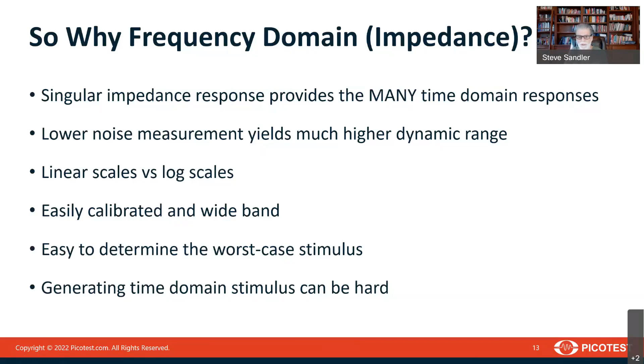So in a vector network analyzer, we don't actually have to worry about generating that stimulus, and in time domain we do. And most of the time we're measuring low impedance. That's not always true, but most of the time, at least in power, we're measuring low impedance. That means we're using something called the two-port shunt-through method. That can be really challenging, especially when you get down to really low measurements. With careful attention, you probably can get there.